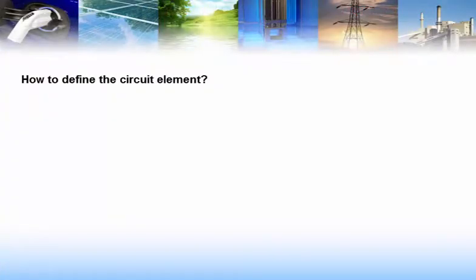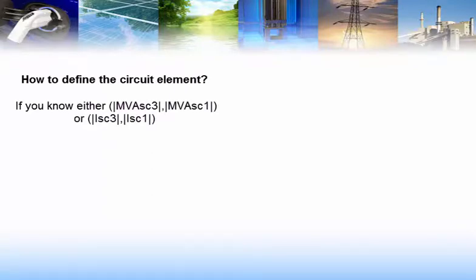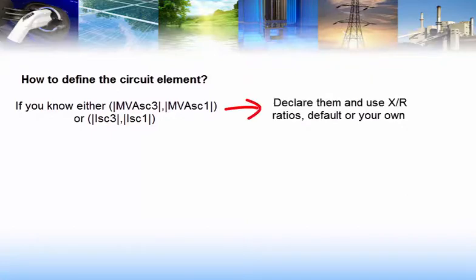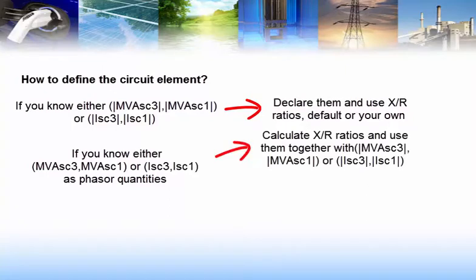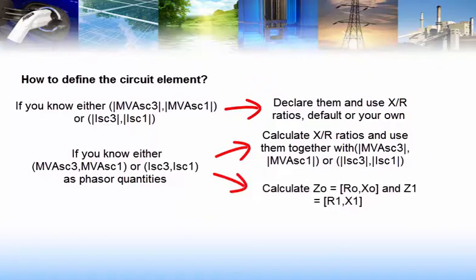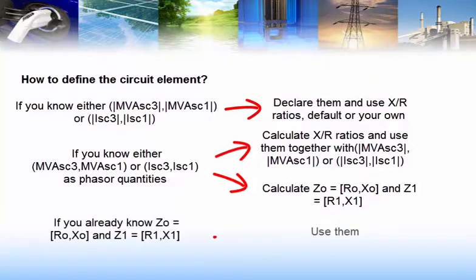To summarize this final discussion, you have three options to define the vSource element. If you know either the module of MVASC3 and MVASC1 or the module of ISC3 and ISC1, you can declare them and use the OpenDSS X over R default ratios or you can define your own. If you know either MVASC3, MVASC1 or ISC3, ISC1 as phasor quantities, you can calculate the X over R ratios by using the equations that we have shown and use them together with these parameters. Or, you can calculate Z0 and Z1 by using the equations that we have shown and specify the vSource element with them. And finally, the easiest way, if you already know Z0 and Z1, just use them.